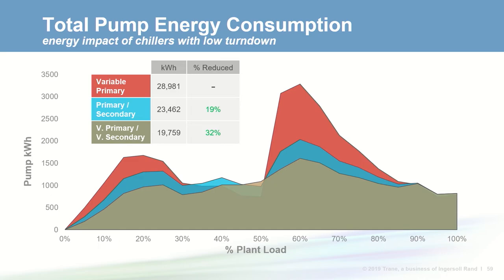This comparison assumes chillers have very limited turndown, which penalizes the variable primary flow system. If designed properly, a variable primary flow system can be very efficient. The takeaway is: you have flexibility to design efficient systems. If a chiller has a high minimum flow and cannot be modified to support a VPF system, choose a different pumping configuration. Alternatively, if you want a variable primary flow system, push the manufacturer to supply a chiller that meets your system requirements.